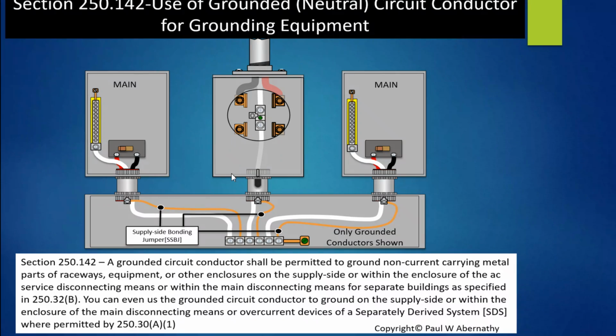All right, now let's talk about 250.142, which is so common in meter enclosures, and it really saves you a lot of money in your installation. Now, we love for you to use wire, but there are some examples where you don't need to have the supply side bonding jumpers, where you could actually use the grounded conductor for that connection. Now, you still use the supply side bonding jumper in the example that I'm going to show you here.